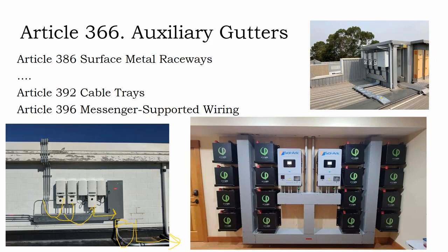And so what the gutters do is allow you to grossly simplify all your cabling coming in and out of the various conduit runs. It also gives you these nice and straight little short stubs between one section to the next, so that you don't have to deal with all the complicated bends and parts and fittings. But this sort of stuff is best pre-designed.